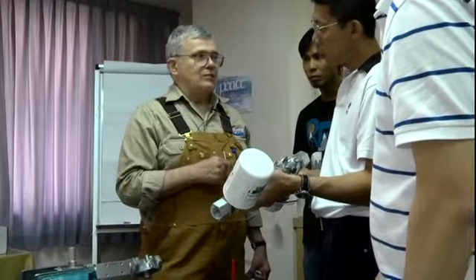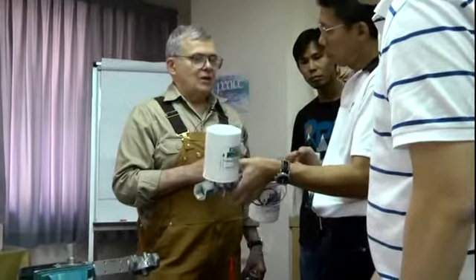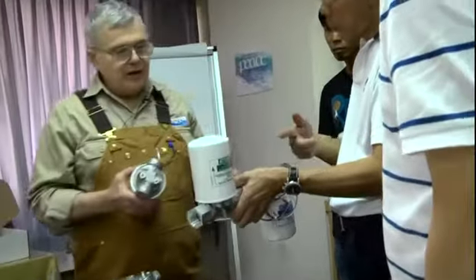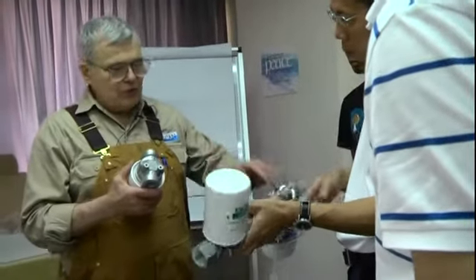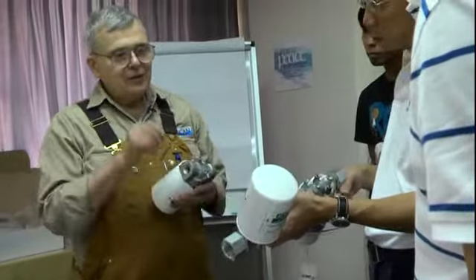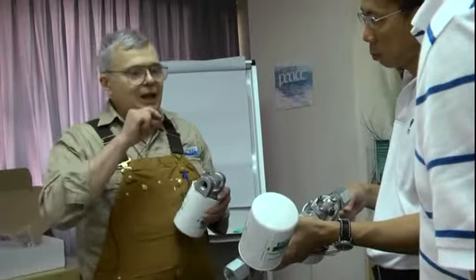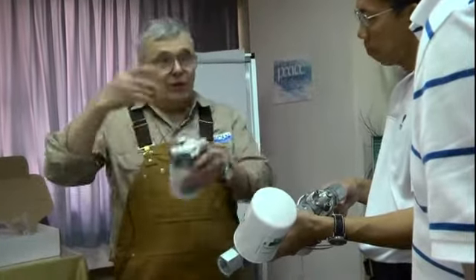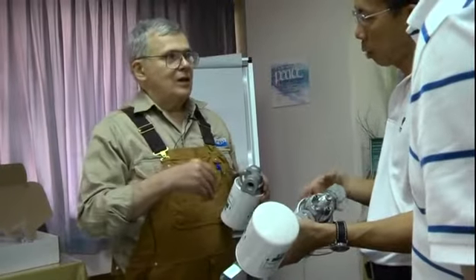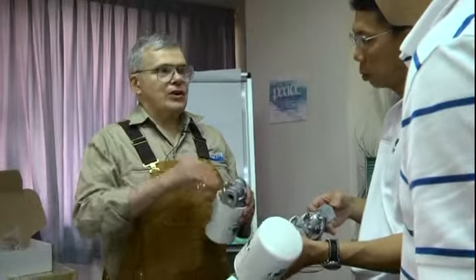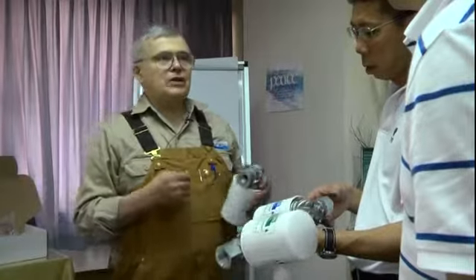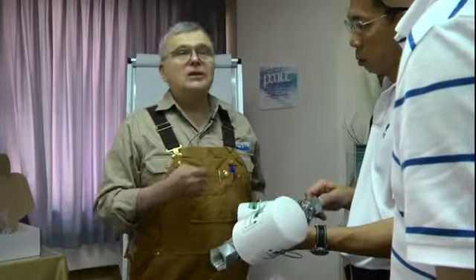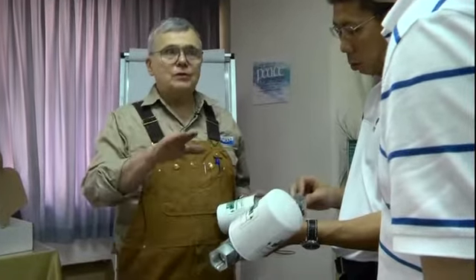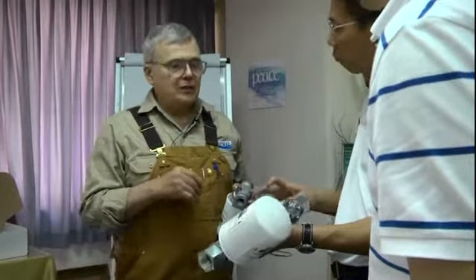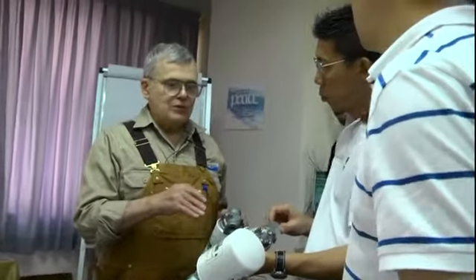No, that one doesn't trap any air. Yeah, but what does it do on the inlet? Oh, well, that comes in, and there's a tube assembly in there with a bunch of holes in it, and the fuel is coming in all churned up. Well, it straightens it out. It gets rid of the turbulence. It makes the flow what they call laminar. Laminar flow is a smooth flow with no turbulence. So it smooths the flow of the fuel.